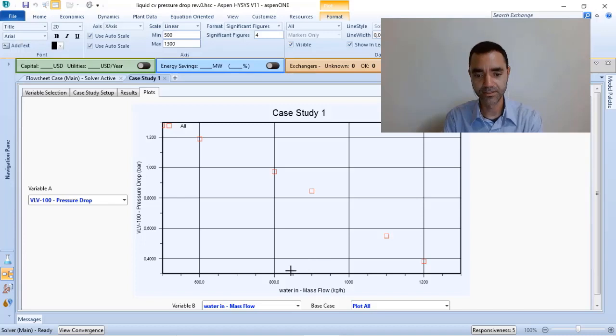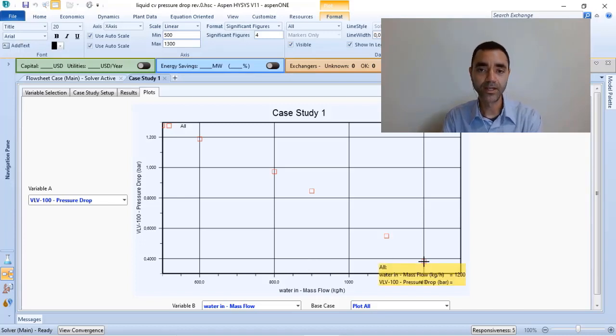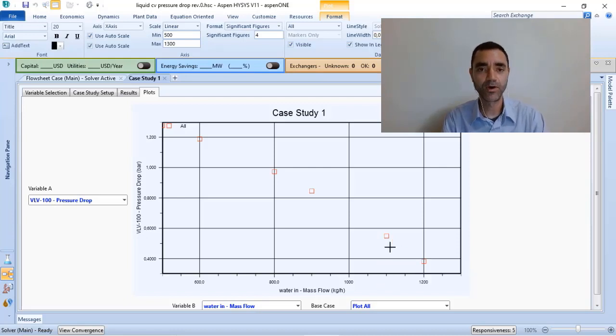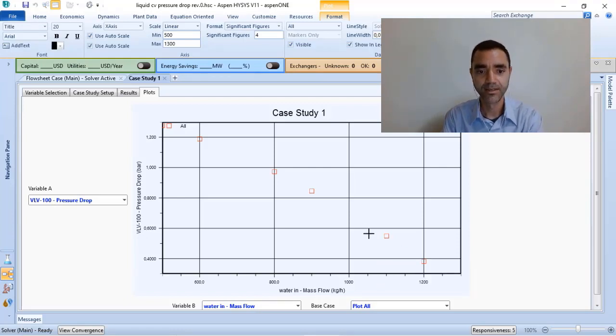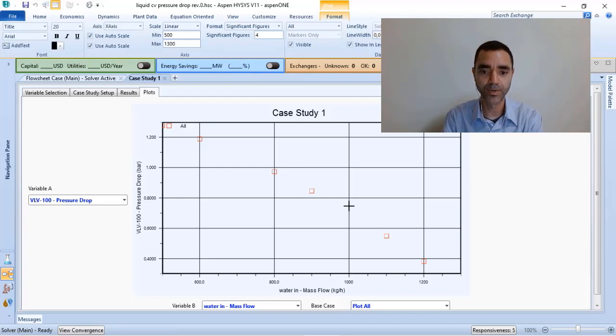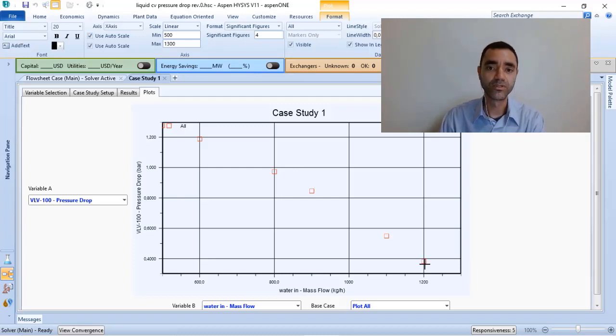Of course, you can see that as I increase the flow, the pressure drop available in my control valve decreases, because I have more pressure drop in the pipelines. To compensate the pressure that I lose in the system, I need to reduce the pressure drop in my control valve.